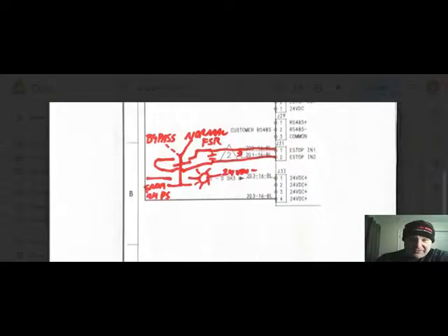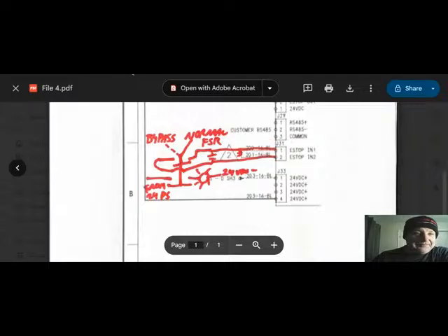Again, it doesn't even have to be a light. It could be an input into the customer's DCS that has a warning up on their computer screen saying, hey, this fire suppression relay and the compressor's been bypassed. Could be a warning light in the maintenance office. I mean, it's literally, because we're supplying this contact and it's a dry contact, whatever power we bring in from wherever, that power can travel back out to wherever we need it to go. You're pretty much limited by your imagination on that one. So yeah.